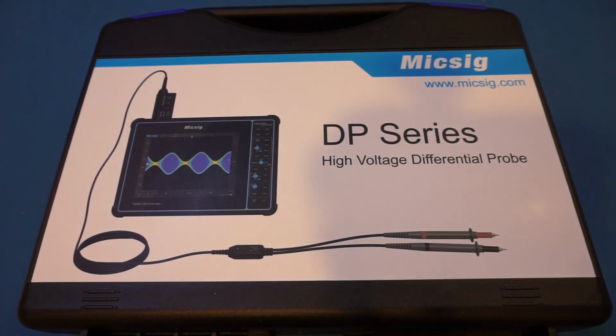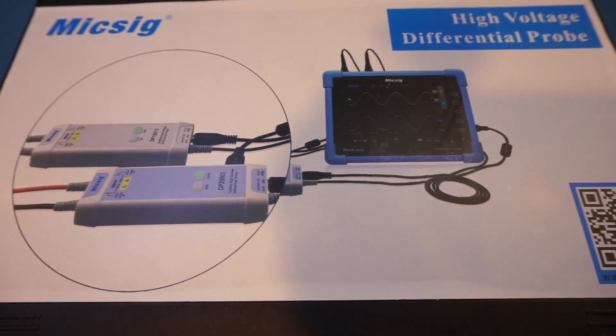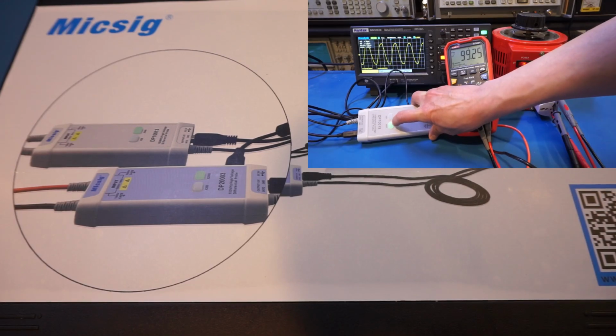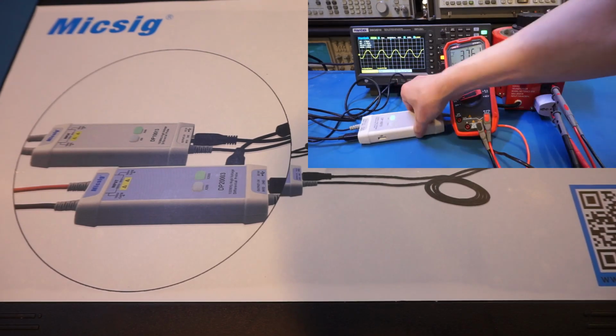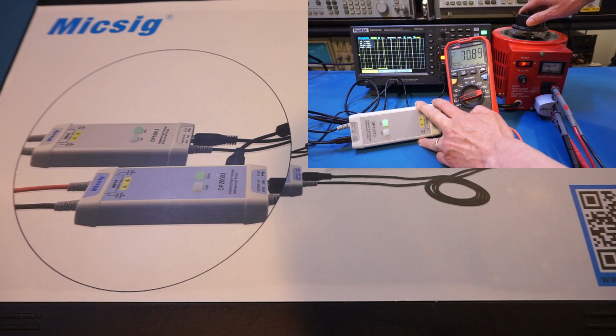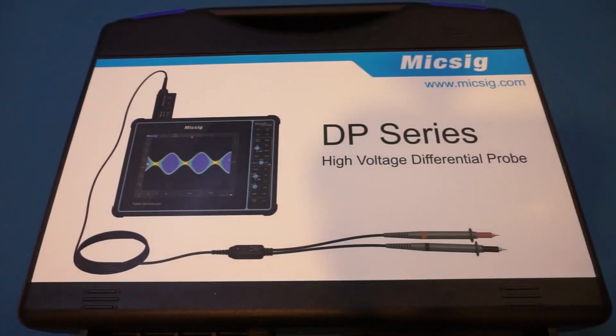If you recall, I reviewed a Micsig DP100 series differential probe in one of my previous videos. That probe was a DP113, a 100 MHz bandwidth probe that can measure high voltage signals up to 1300 volts. I have used that probe many times since I reviewed it, and I can tell you having a differential probe when troubleshooting mains earth referenced live circuits is really essential, as otherwise you could easily short out the circuit if you are not careful and jeopardize your personal safety. It could also lead to extensive damages to the circuit under measurement, your probe, or even your expensive oscilloscope.